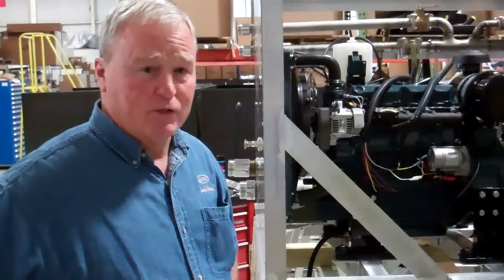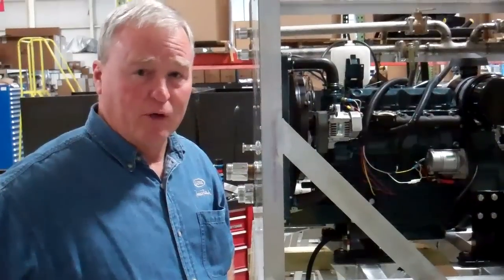It's a 250 GPM pump at 150 PSI. It meets all the criteria for the 1901 for initial attack vehicle. So it's got stainless steel plumbing. It's got a Class A foam system on it. Like I said earlier, 300 gallons of water and 10 gallons of foam. Great unit and it's going to go into a quick attack truck for an initial attack vehicle.